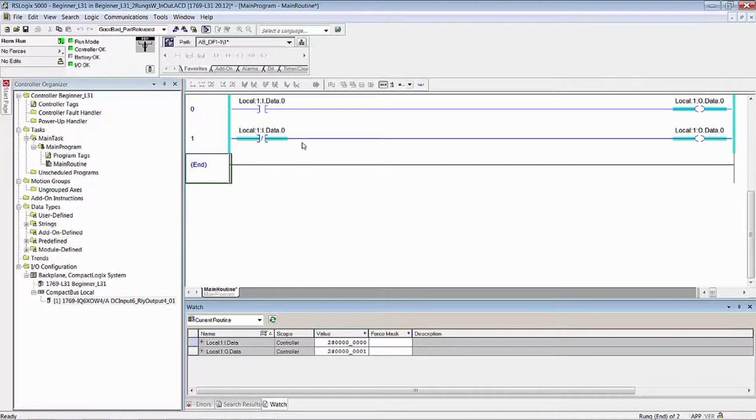With the Logix engine, unless you go through some special efforts to prevent scan-dependent logic like this, there is a way to make this work. Either way, I would never use two OTEs executing against the same bit in memory. But we could buffer our I/O, and we'll discuss that in a later lab. That's in this volume. And you wouldn't see this intermittent behavior. Last man would always win. But when you have asynchronous I/O activity in memory, then the memory can get updated in between these two rungs.